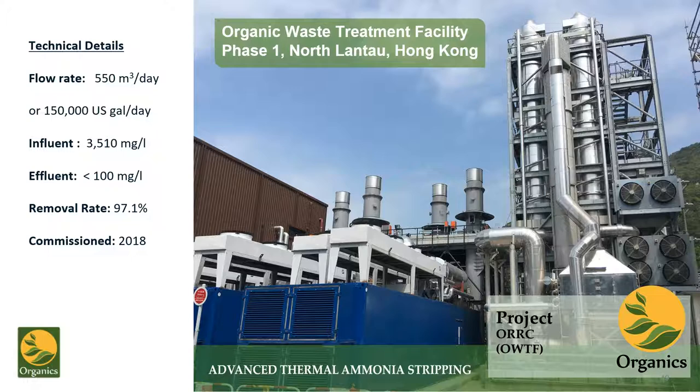So the ammonia stripper is located along the effluent line from the facility and is primarily concerned with discharge compliance. And the placement option, for example, would be at option three, mentioned earlier in the presentation on the anaerobic digester slide. And at this place, it really gives it the lowest possible discharge level, which is under 100 milligrams per liter.